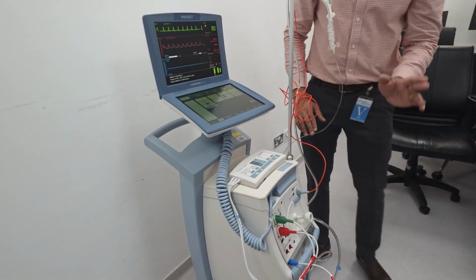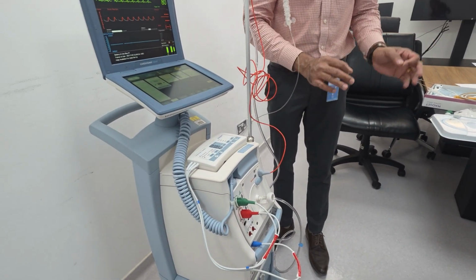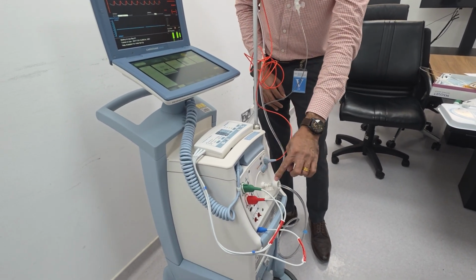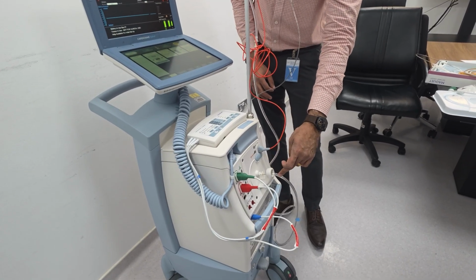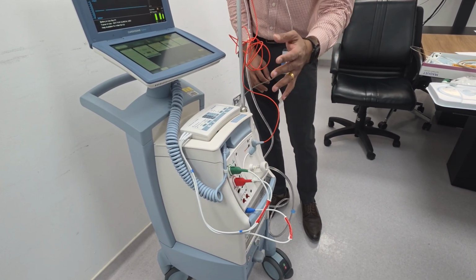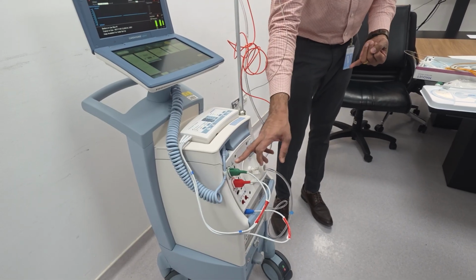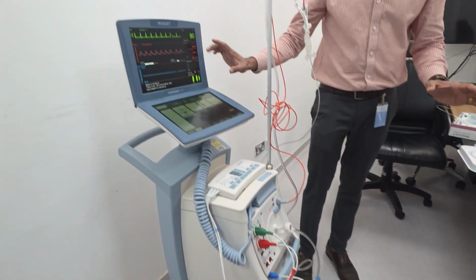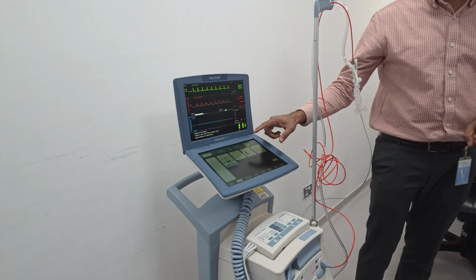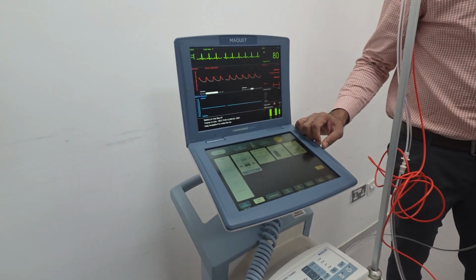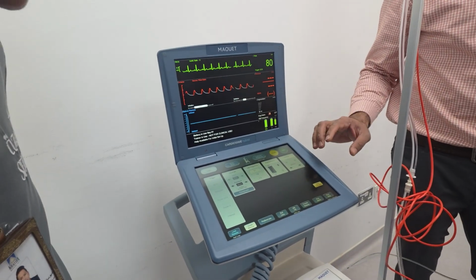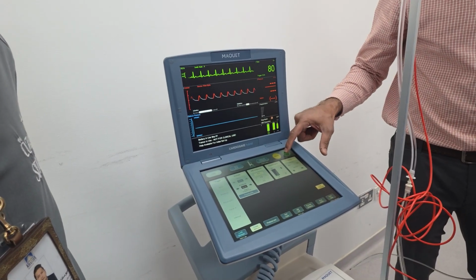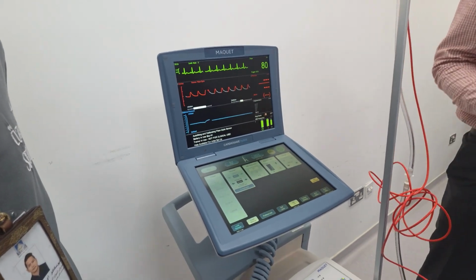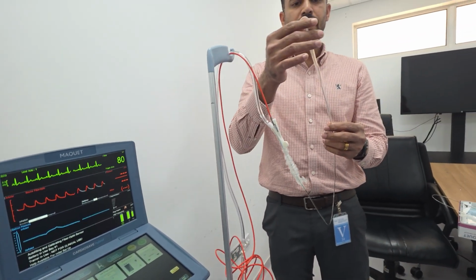Now we did everything. So basically, it's a very user-friendly machine. Connect ECG, pressure, and balloon, and before you switch on the machine, just three steps. Switch on, 1, 2, 3, and nothing more to do. Just press start. If you are using non-fiber, you know you have to do the zero, right? Here we are using fiber. Just press start. It will do auto filling, same as the CS300. A deep vacuum.